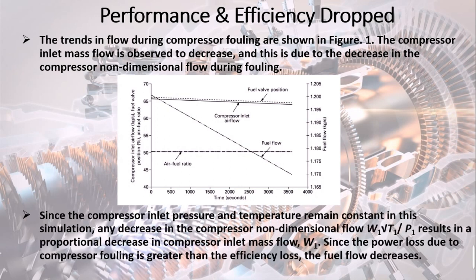Since the compressor inlet pressure and temperature remain constant in this simulation, any decrease in the compressor non-dimensional flow W1√T1/P1 results in a proportional decrease in compressor inlet mass flow W1. Since the power loss due to compressor fouling is greater than the efficiency loss, the fuel flow decreases.